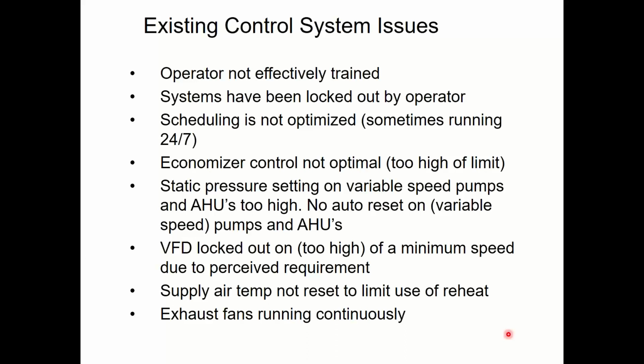And it doesn't even have to be a building automation thing. It could be a physical thing, right? There's plenty of times that I've gone to buildings and seen a 2x4 jammed up inside an outside air intake damper, propping it open. Well, how the hell is the control system supposed to shut the damper tonight? Or tomorrow night? Or for the next month? Oh, it's not, right? The scheduling is always messed up on all these buildings. There are so many buildings that are running 24/7, even though they have the ability to put a schedule in, because somebody didn't want to deal with it.